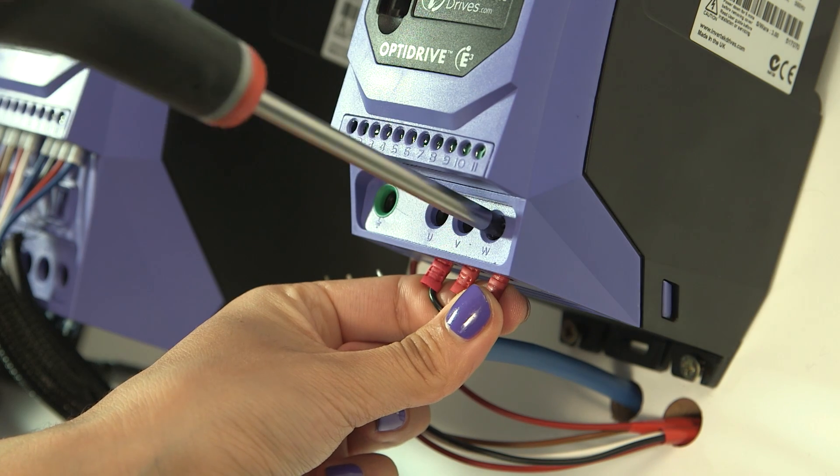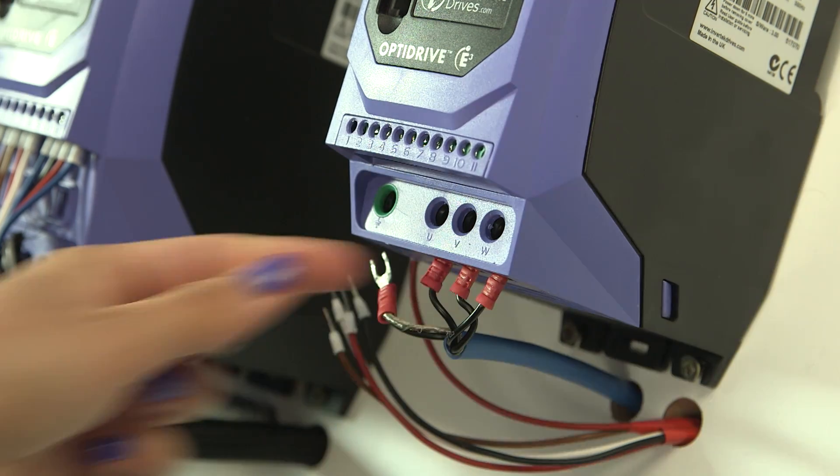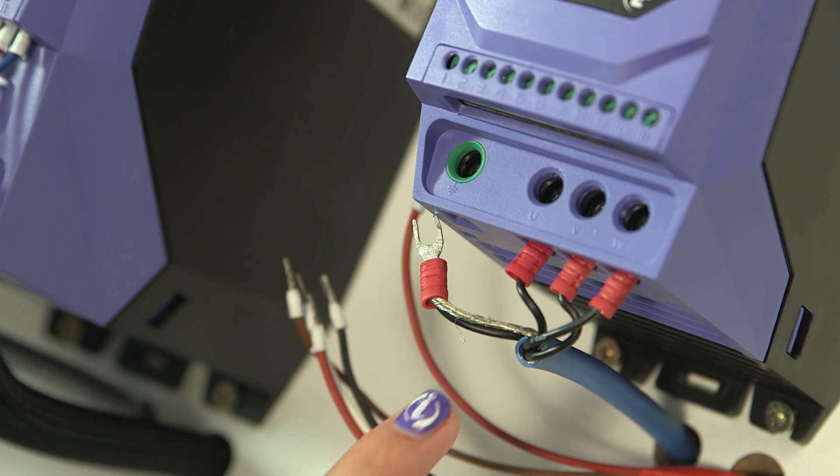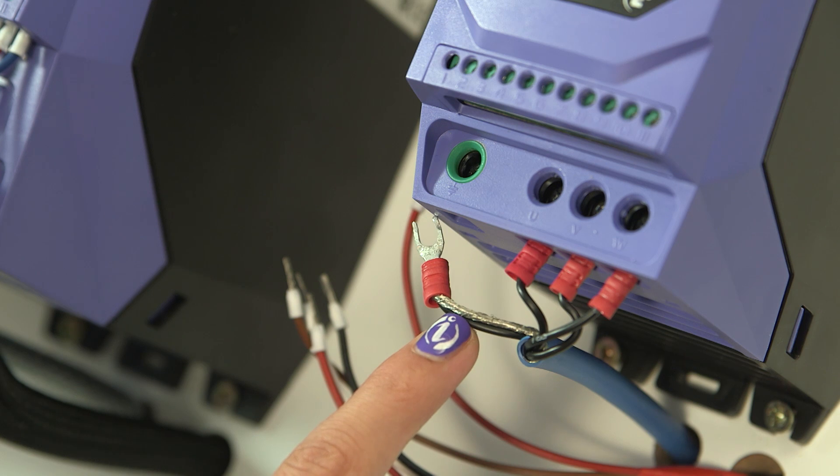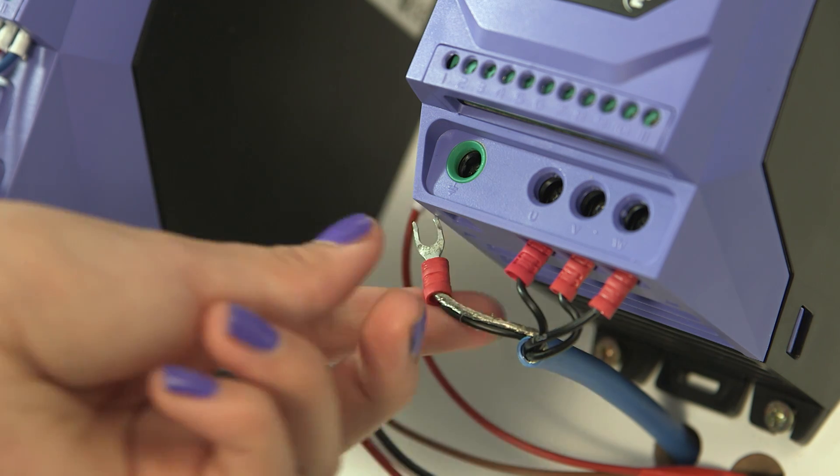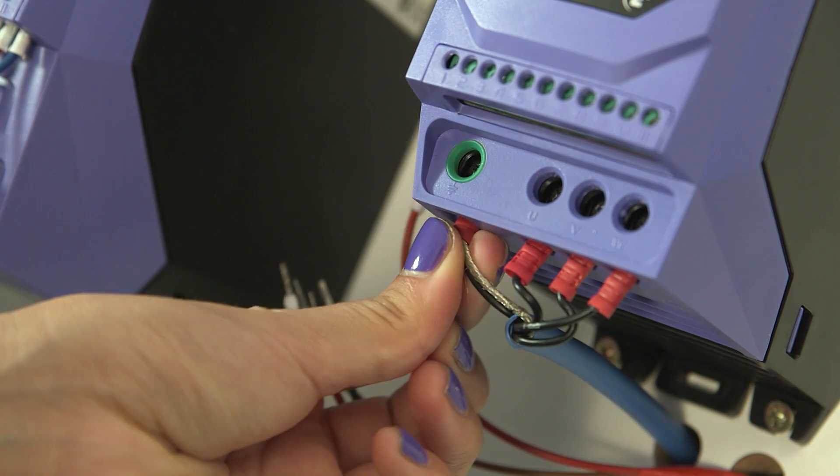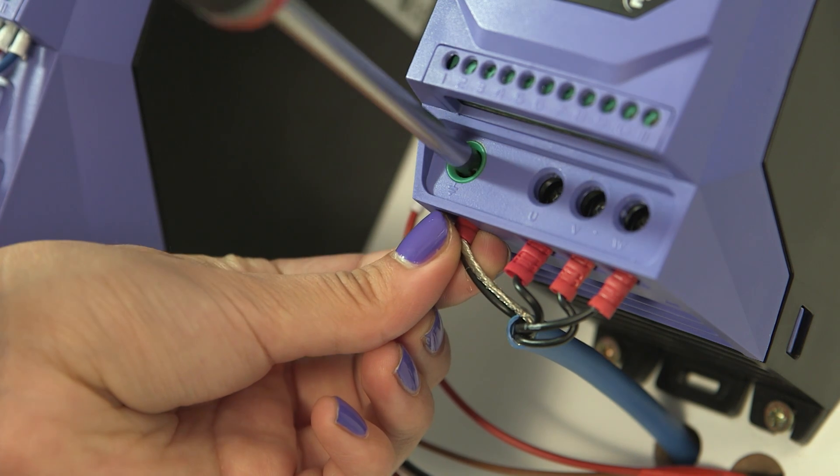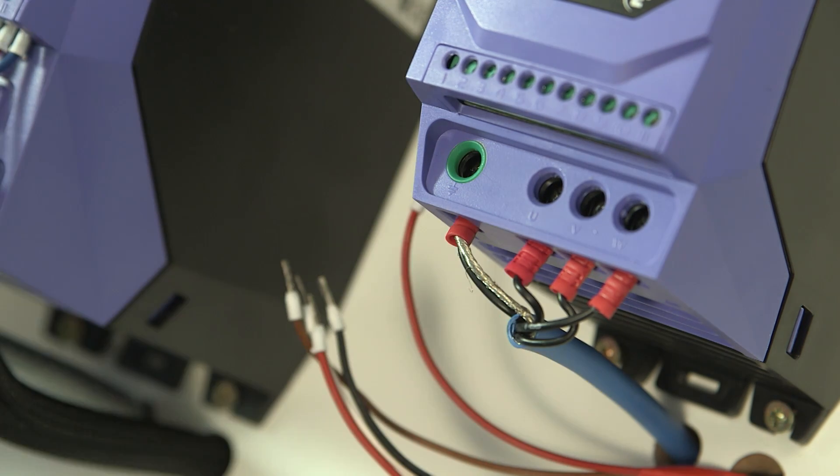The motor will run clockwise looking on shaft if correctly connected. Always use screened cable from the drive to the motor, because the high voltage and high switching frequencies in this cable can easily cause interference. Earth the motor locally and through the cable connection as well as the screen.